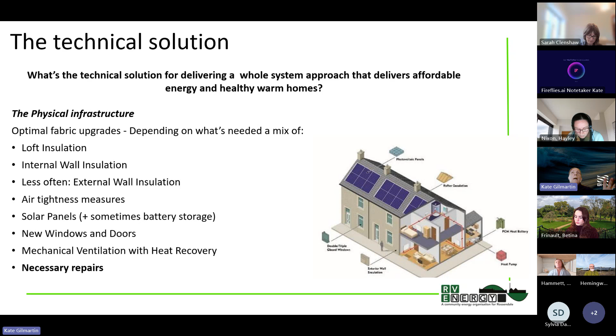Then for the heat itself, we're looking at an ambient loop ground source heat pump. Essentially this is buried pipework in the street where each borehole could go up to about 150 metres and should serve 2 terrace properties. That borehole takes heat out of the ground and warms water to about 12 degrees C.